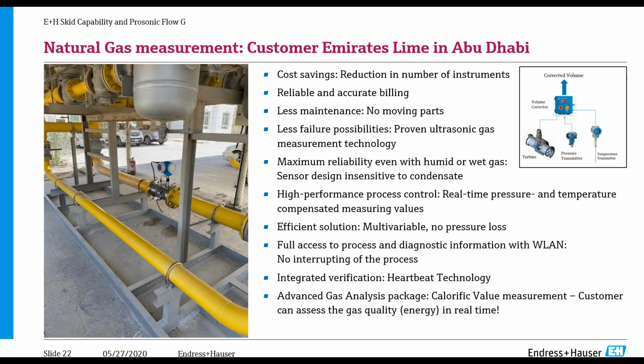This was a field trial that we had in the UAE. This was for the replacement of turbine meters. They had difficulties with their turbine meters because of mechanical wear, and they wanted something with no moving parts that was more reliable in the application. They also liked the fact that we had our integrated pressure and temperature here. And this was actually going to be used for billing. We do not have custody transfer approvals on this meter, but when two parties agree they want to use it for billing, they go ahead. This one is going into a natural gas application, eliminating any moving parts, so very maintenance free versus what had been previously in the application.